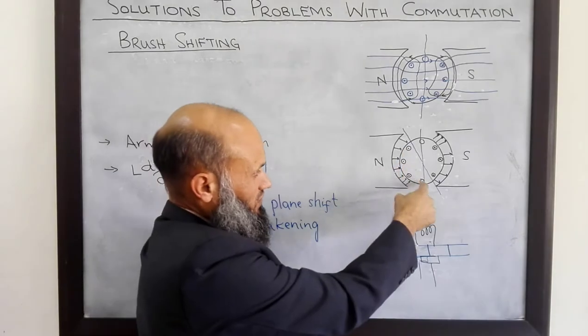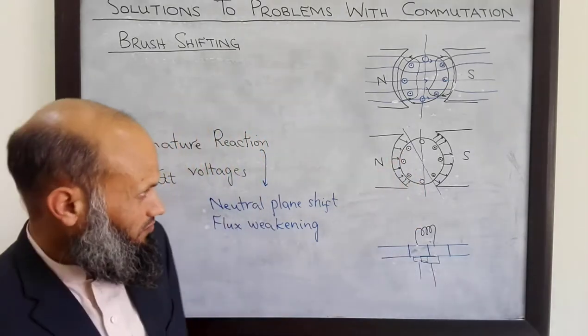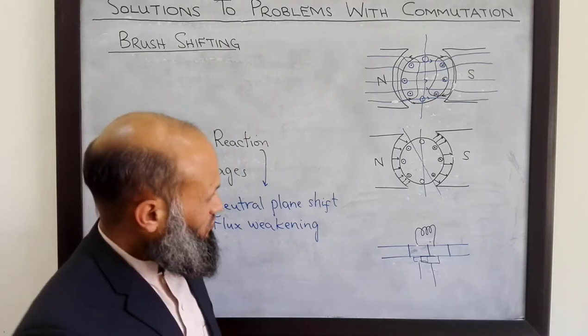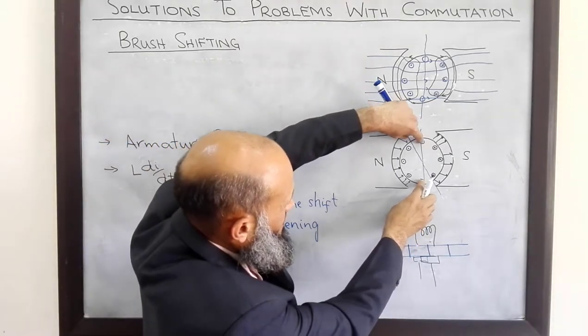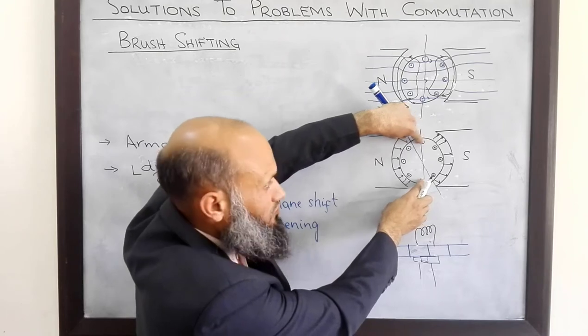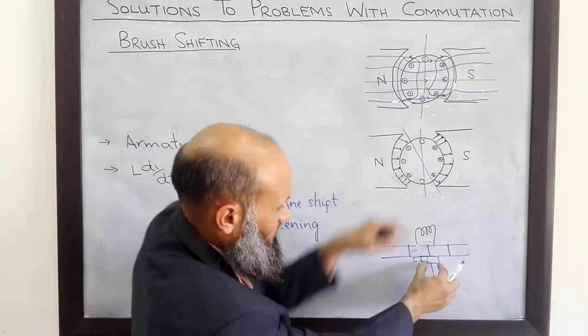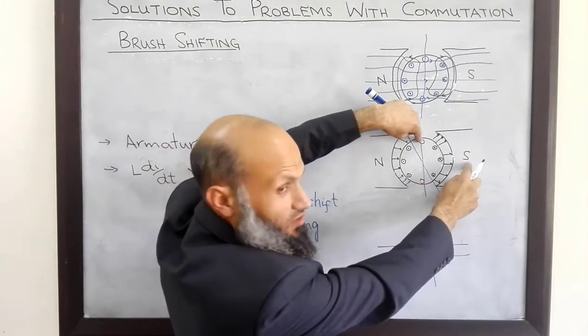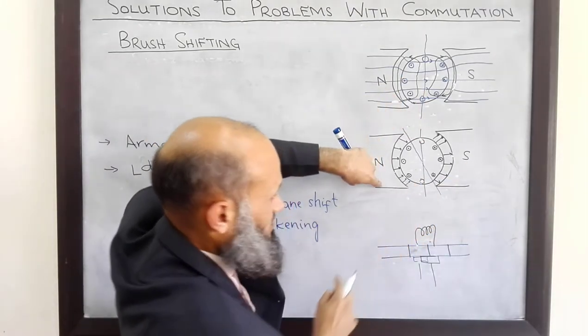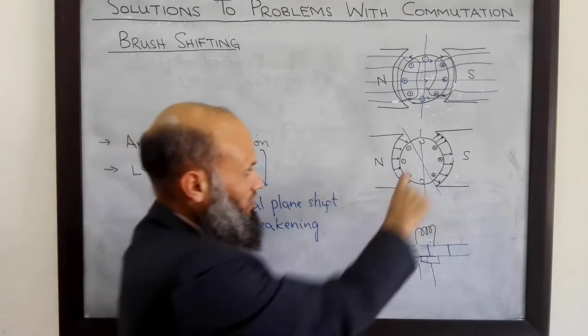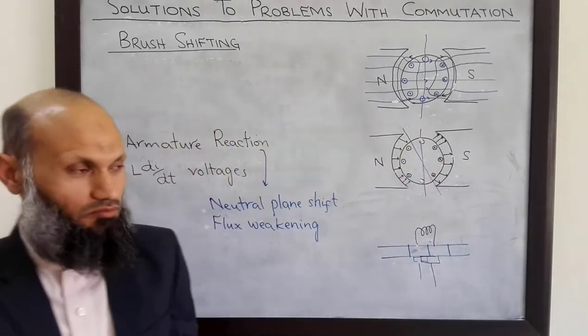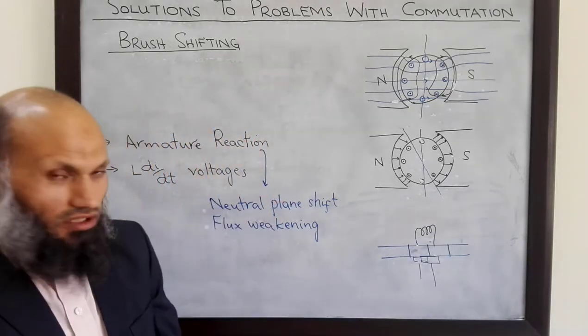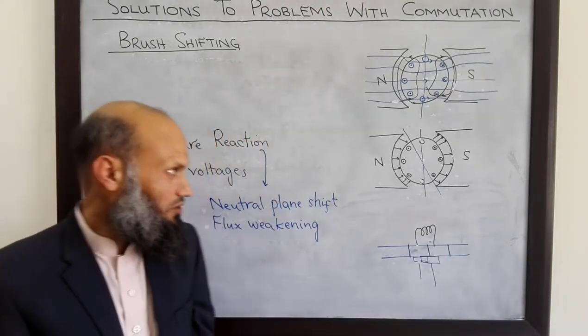However, due to armature reaction, this neutral plane has shifted. We were assuming that no voltage would be induced in the coil being shorted. Now, this conductor is under the influence of the south pole and this conductor is under the influence of the north pole. So in both conductors, voltage will be induced, and shorting the two ends of this voltage source will be problematic.